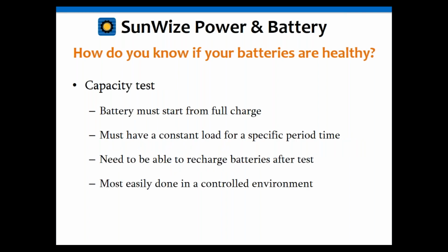The only other good method for that is a capacity test, and this is not easy to do on a standalone system. If you've got a UPS system or some other type of system with a generator or something like that, then it's an easier test to do, because what you have to do is you have to start with the battery at a full state of charge. So the battery has to be fully charged to begin with. Then you have to put a constant or specific load on it.